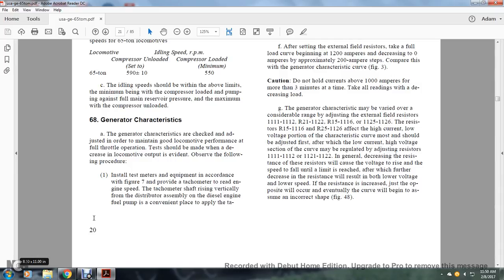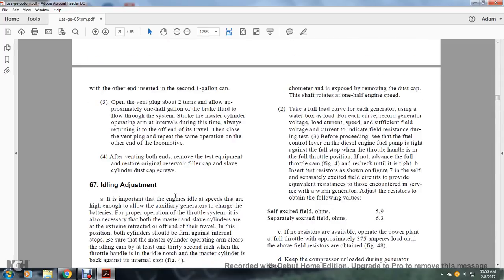Section 68, Generator Characteristics. The generator characteristics are checked and adjusted to maintain good locomotive performance at all throttle positions. Install test meters and equipment per figure 7, including a tachometer to read engine speed. The tachometer shaft rises vertically from the distributor assembly on the diesel engine fuel pump. Take the full load curve for each generator using a water box load, recording generator voltage, load current, and speed with sufficient field voltage and current. Before proceeding, ensure the fuel control of the diesel engine fuel pump is tight against the fuel stop with the throttle in position. Adjust the resistors to obtain the following values: self-excited field ohms 5.9, separately excited field ohms 6.3.